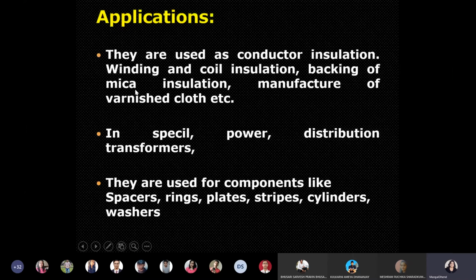So in special types of transformers, power and distribution transformers, pressboards will be used. They are also used for components like spacers. Spacers means if you want to increase the distance between, suppose, wires. Suppose if you see overhead transmission lines, you can observe that between the two transmission lines a distance has to be maintained. If proper distance is not maintained, then ionization may take place, the air between the two transmission lines may ionize, because air is used as a natural insulation between the two conducting wires.